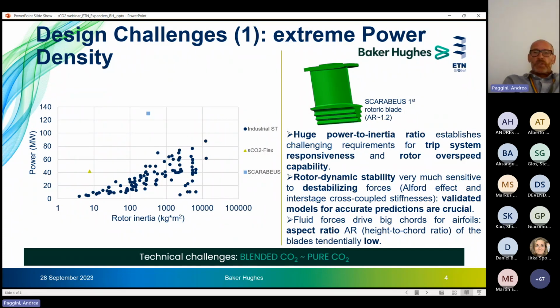Which are the challenges? One immediate criticality is that in case of loss of load, so essentially an event of a generator breaker opening, for example, or even worse, in case it's applicable, loss of load and inertia, so a coupling failure scenario, the overshoot speed reached by the rotor is well above the typical values encountered in steam turbine trains as a result of the large power density. And so it establishes very challenging requirements for the responsiveness of the trip system and for the overspeed capability of the rotor.